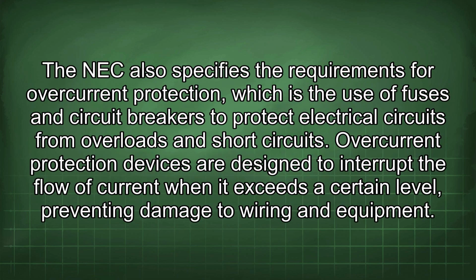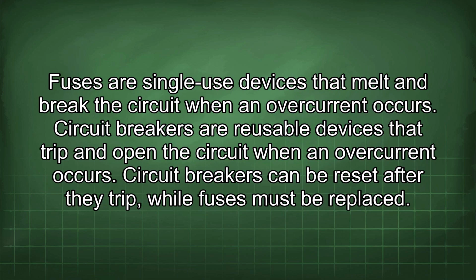The NEC also specifies the requirements for overcurrent protection, which is the use of fuses and circuit breakers to protect electrical circuits from overloads and short circuits. Overcurrent protection devices are designed to interrupt the flow of current when it exceeds a certain level, preventing damage to wiring and equipment. Fuses are single-use devices that melt and break the circuit when an overcurrent occurs. Circuit breakers are reusable devices that trip and open the circuit when an overcurrent occurs. Circuit breakers can be reset after they trip, while fuses must be replaced.